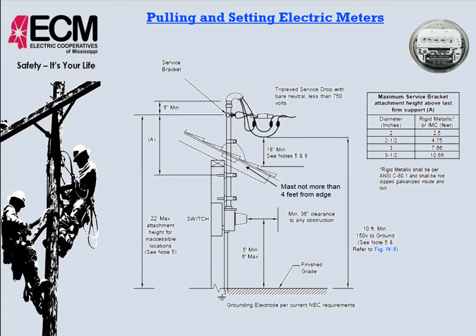One of the first things we'll look at is your drip loop above the roof. Has to be a minimum of 18 inches above the roof, inside of 6 feet. Okay, so 6 feet from this pipe, say the service was entering from the side and ran along the roof for a certain distance before it got to the weatherhead. Inside of 6 feet from this pipe, the minimum distance your triplex can be is 18 inches. And even here in this situation where it comes in square, your drip loop cannot be any closer to the roof than 18 inches.